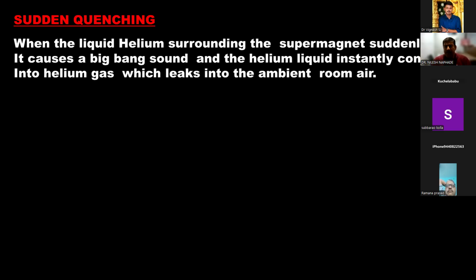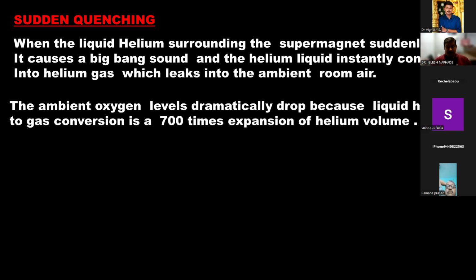The liquid helium instantly converts into helium gas, which leaks into and mixes with the ambient room air, very instantaneously. And believe me, the ambient oxygen levels dramatically drop, because the liquid helium to gas conversion is a 1:700 expansion. 1 ml of liquid helium becomes 700 ml of helium gas. So whatever helium jacket surrounds the magnet, multiplied by 700 is the concentration of helium in that room suddenly. Suddenly the oxygen in the ambient air drops.